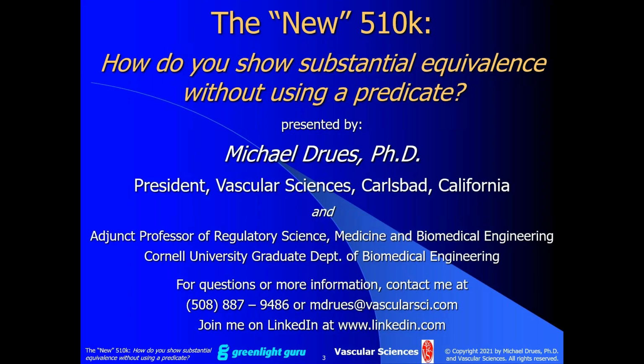When it comes to the PMA, that's a little more interesting because the PMA is for class 3 devices, obviously. And you can't use a predicate in the regulatory sense to get a PMA device onto the market. However, if you have a PMA device, let's say a bare metal coronary stent, for example, that is indicated for atherosclerosis, we have dozens of those stents on the market and they're all class 3. And there's not a snowball's chance here in Southern California that you're going to get a bare metal coronary stent through the FDA and onto the market for atherosclerosis with anything other than class 3.